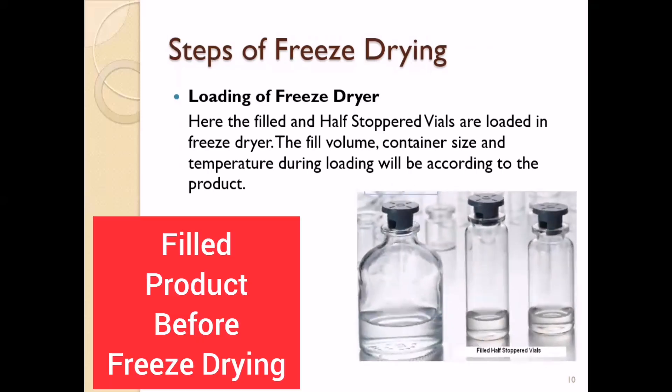Here we can see filled, half-stoppered vials in liquid state before subjecting them to the freeze-drying process. The stoppers are half-stoppered — not fully seated. The reason for this is that during the freeze-drying process, when the product undergoes drying, moisture needs to escape from the product. A full stopper would completely seal the vial and not allow vapor to escape during drying, so half-stoppering is required.